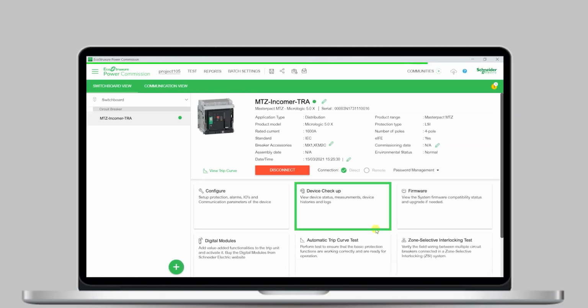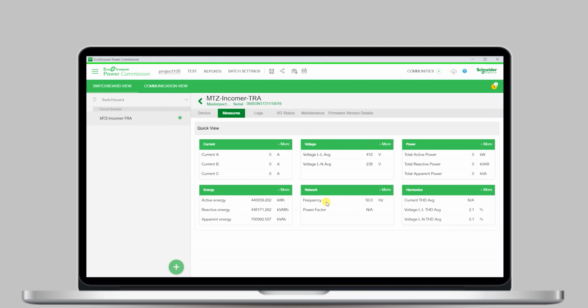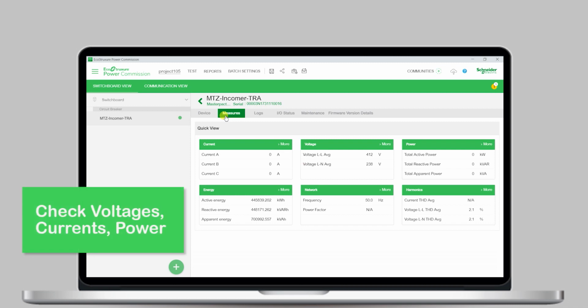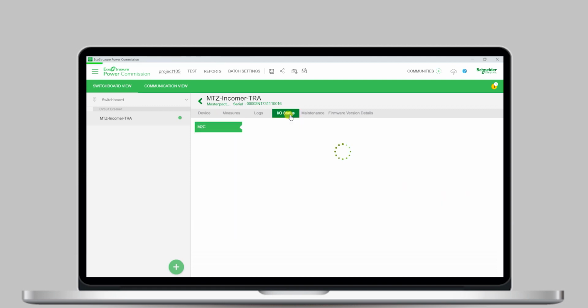Now that the circuit breaker is properly connected to the laptop, let's begin with the basic testing functions in order to quickly check up the breaker status. This allows you to, with one click, evaluate the functioning of the Micrologic control unit. Here, you will be able to see the voltages, currents, power. If you see some strange values, like negative current or wrong power factor, you know there has been a mistake and you can then fix it.